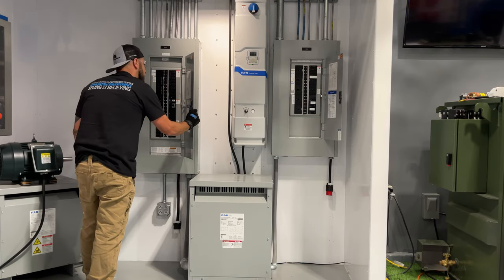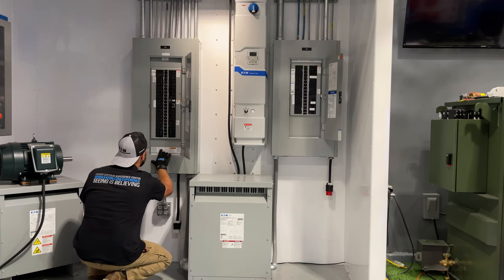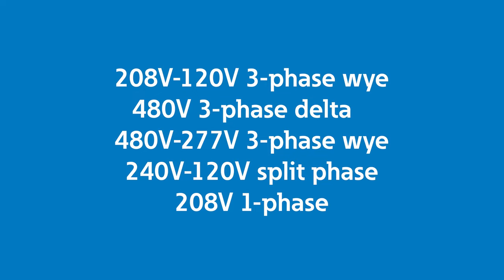First, you should look at the site location where the SPD is to be installed. During this step, you should check and verify the voltage level and number of phases in the panel and grounding type for the services feeding this panel. For example, the voltage may be 208/120 3-phase Y, 480 3-phase delta, 480/277 3-phase Y, 240/120 split phase, or a 208 volt single phase. Usually, this information should be available on the nameplate of the panel board.